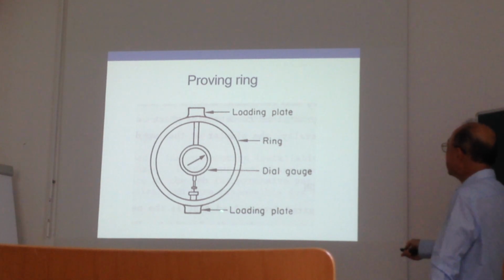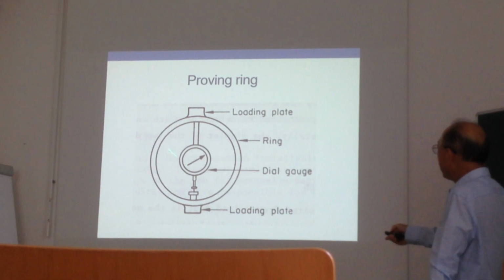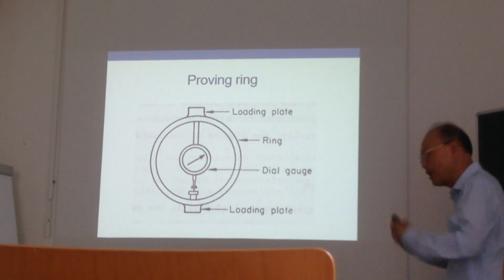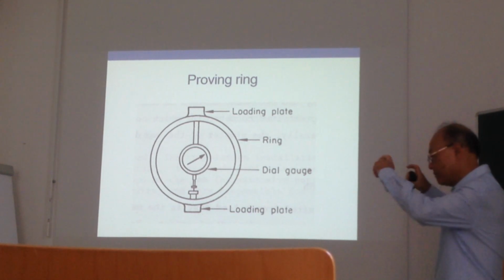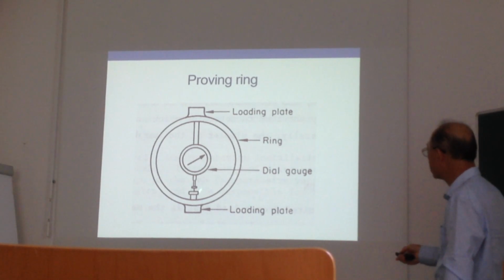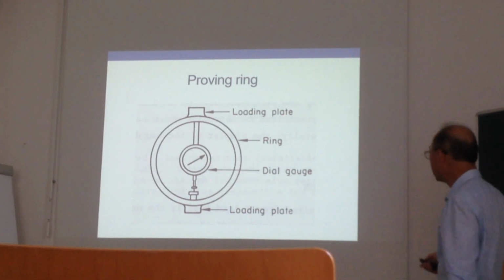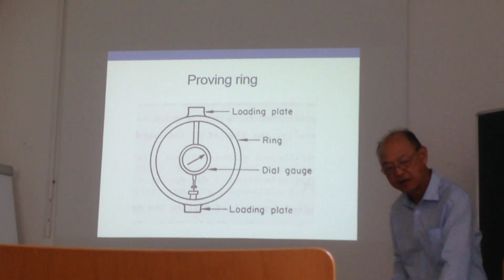So that's the proving ring, just a piece of metal, a ring, with a dial gauge in between. As the ring is compressed by force, it becomes flatter, and the amount of displacement is calibrated to the amount of force experienced. That's the basic idea.